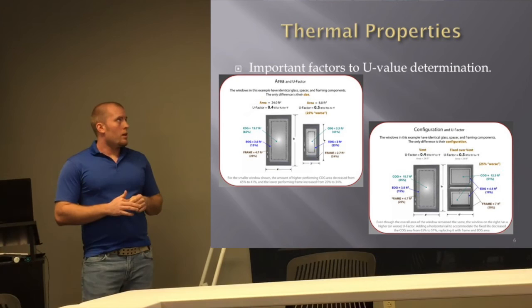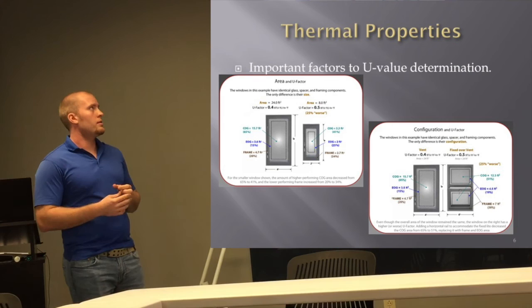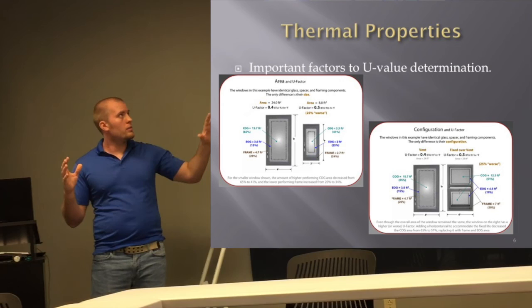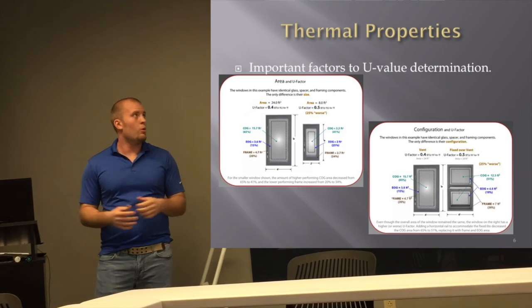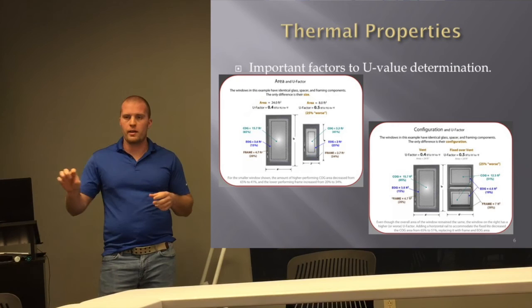For U-value determination, the key theme is more frame equals worse performance. On the left, a large punch window opening has lots of glass; shrinking the glass while keeping the same frame increases U-factor by about 25%. Similarly, adding an intermediate rail to the same size frame — adding more frame to the system — also worsens U-factor by about 25%. These are important factors to keep in mind.